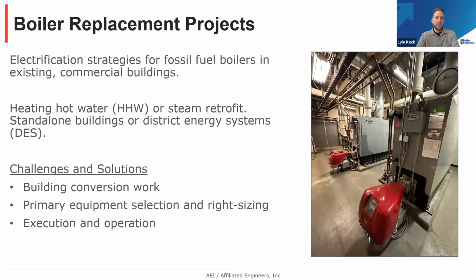Next slide, please. So we're here today to talk about boiler replacement projects, electrification strategies for fossil fuel boilers in existing commercial buildings, with the goal of minimizing on-site fossil fuel use, transitioning over time to clean, renewable, and low-carbon energy sources, and in many cases, improving energy efficiency and reducing operational costs. We're really talking about taking a high-temperature heating hot water system, let's say 180 degrees or greater, or a steam to hot water, or even a direct steam system, and retrofitting that to be able to use lower temperature heat pump-based technologies. The general topics for today are organized into these 3 buckets on the left-hand side. You'll see we'll be talking about building conversions, primary equipment, as well as lessons learned for project execution and operations. And the photo here is a natural gas-fired hot water boiler from the field.